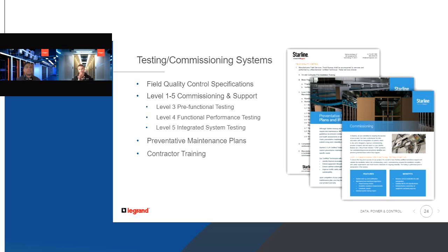So there are 5 levels of commissioning. Pre-functional is typically when you start to really get into the nitty-gritty of it. That consists of inspections prior to busways being energized. There's a set of electrical and mechanical inspections you want to take on those, relating to the busway, open channel, and the high power bus bar as well. Both are pretty similar.